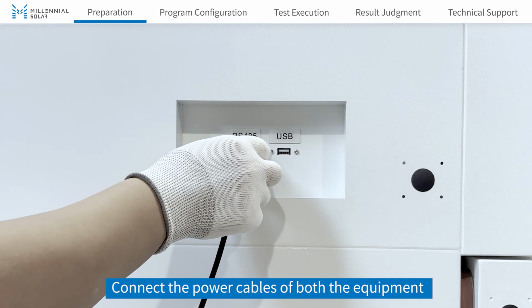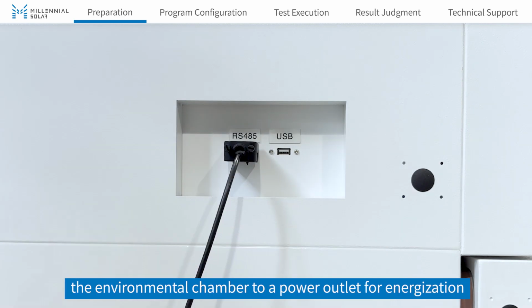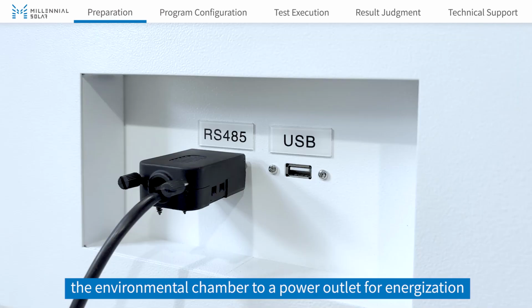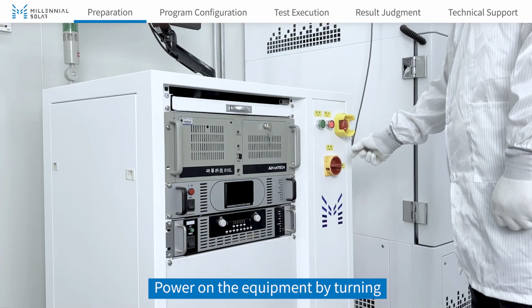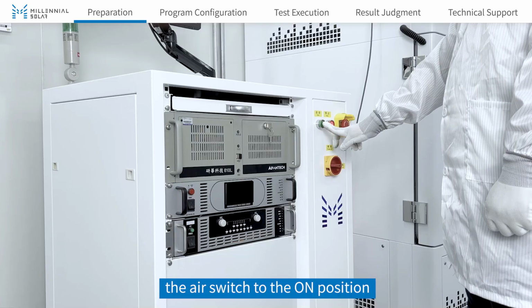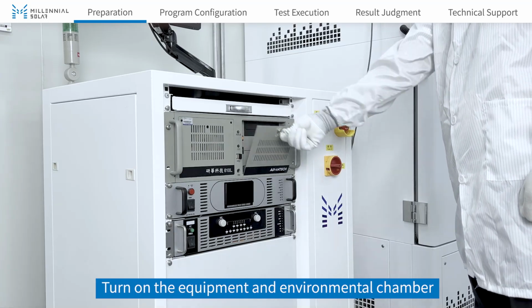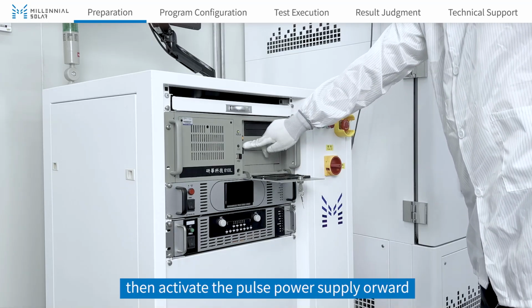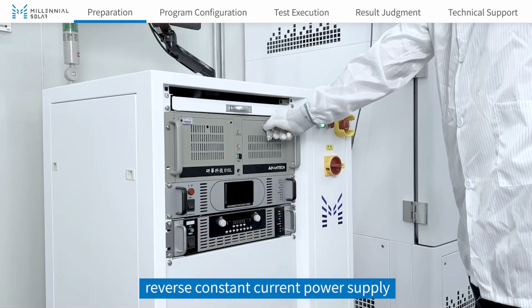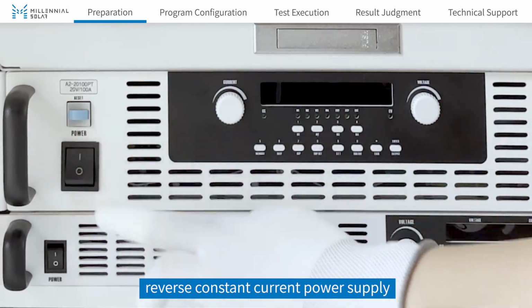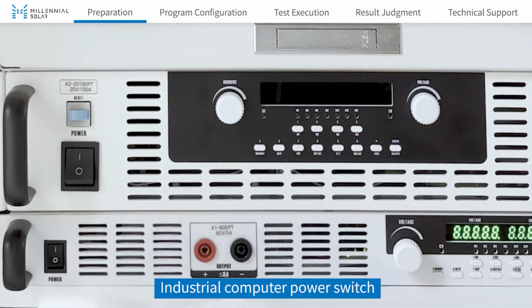Connect the power cables of both the equipment and the environmental chamber to a power outlet for energization. Power on the equipment by turning the air switch to the on position. Turn on the equipment and environmental chamber. Then activate the pulse power supply, forward, reverse constant current power supply, and industrial computer power switch.